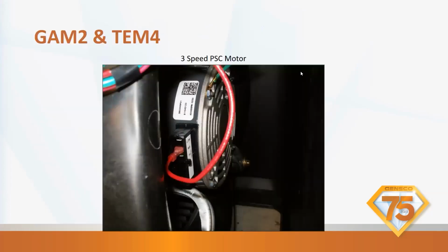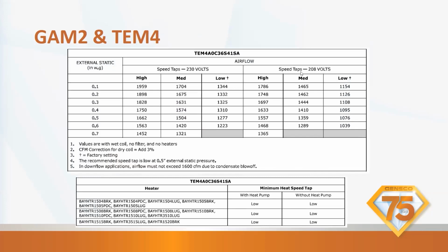This is the TEM4 3-speed PSC motor. You're going to change the speed tap on a PSC by moving the wire. Okay, so this is a single speed unit with a 3-speed motor in it. It's only going to have one wire going to the speed tap, so you're going to change that to whatever speed tap you want. And this is the TEM4. It shows us the speed taps, high, medium, or low, and it shows us the static pressure and what you can expect at those speed taps. So that's for a GAM2 and a TEM4.